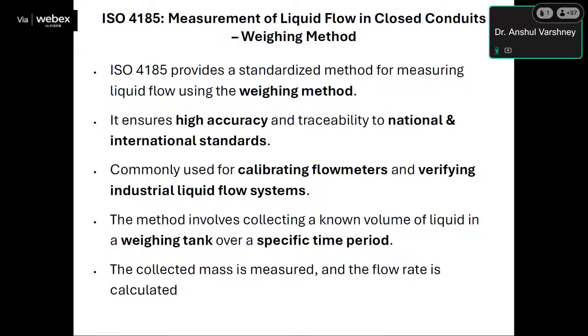The method involves collecting a known volume of liquid in a weighing tank over a specified time period. The collected mass is measured and the flow rate is calculated. Basically, the mass flow rate is directly traceable to mass and time. In calibration, we collect a known volume of water in weighing tanks for a specified time period. That mass is divided by time, which gives the mass flow rate.